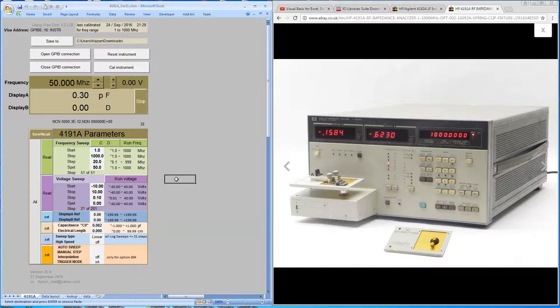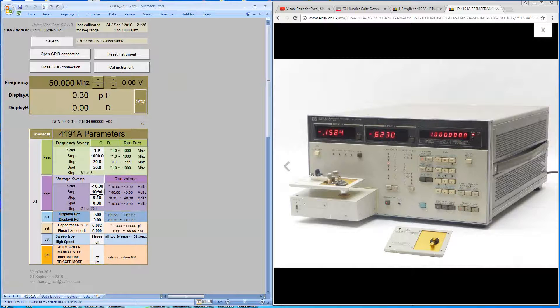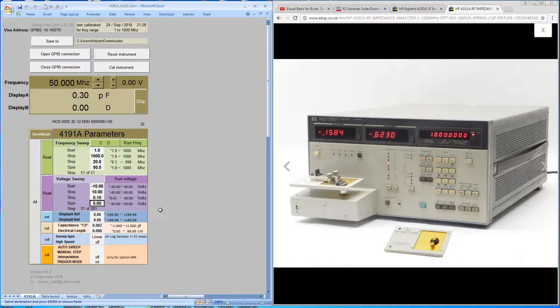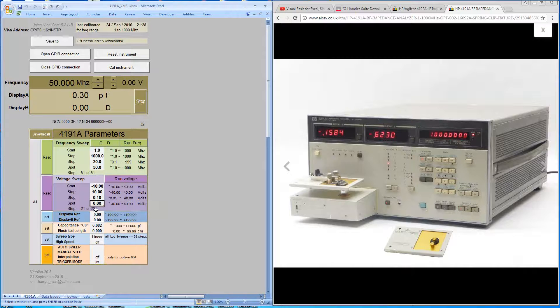This analyzer is also capable of doing a voltage sweep. And so you can set the start and stop voltage sweeps from plus or minus 40 volts. You can set the size of the voltage step and the point of the parked voltage that it'll be measuring at. And it'll give you the number of steps.